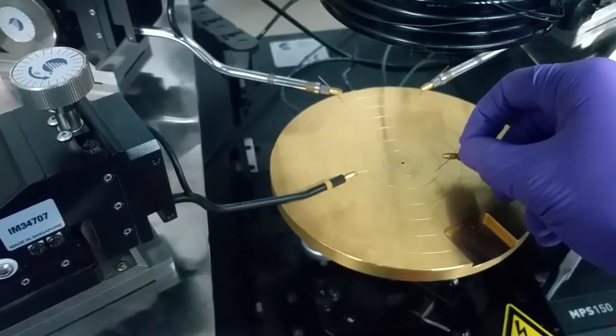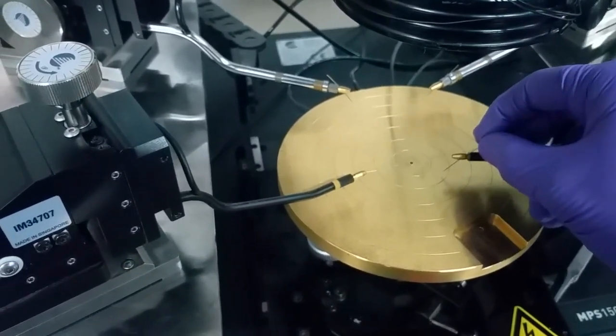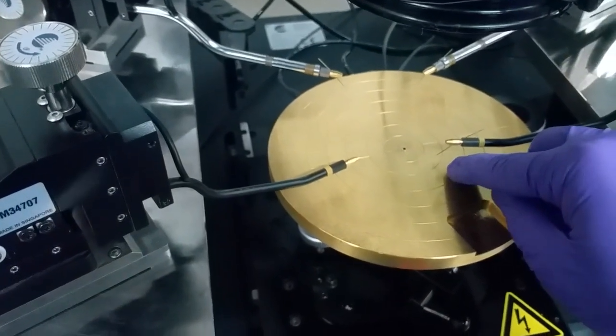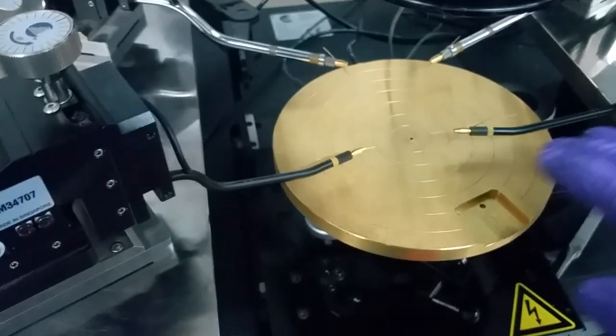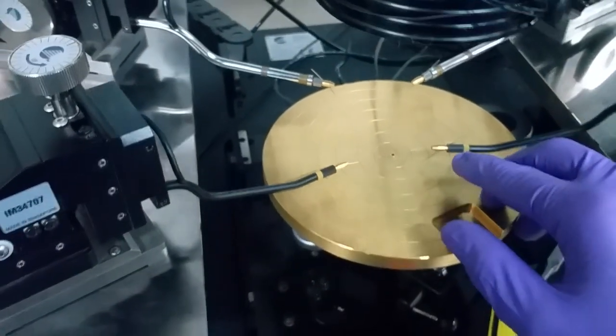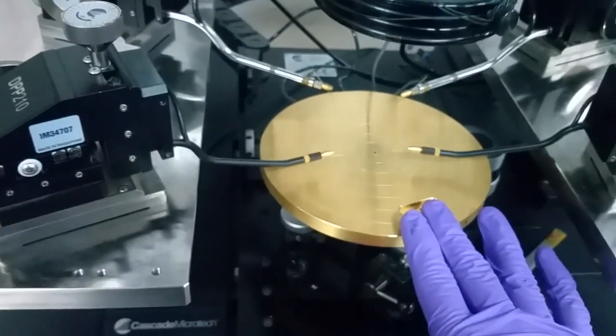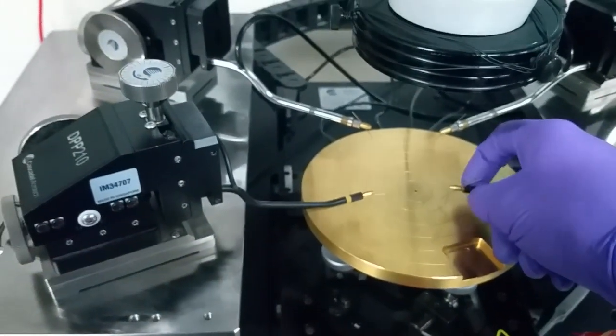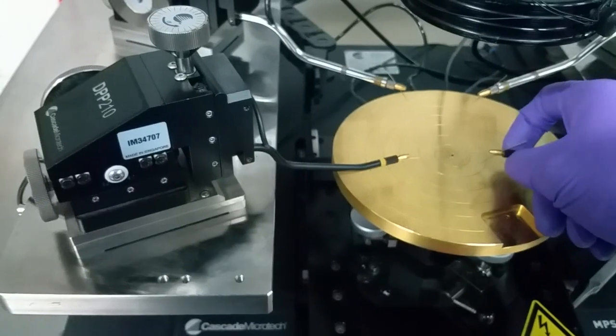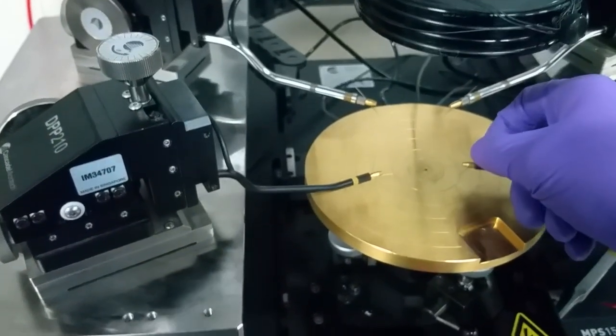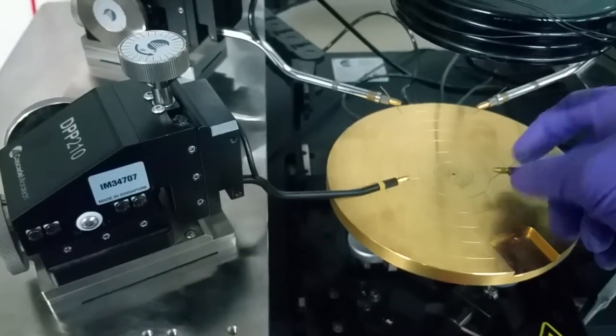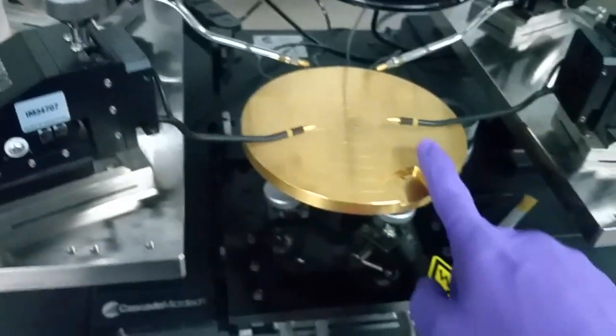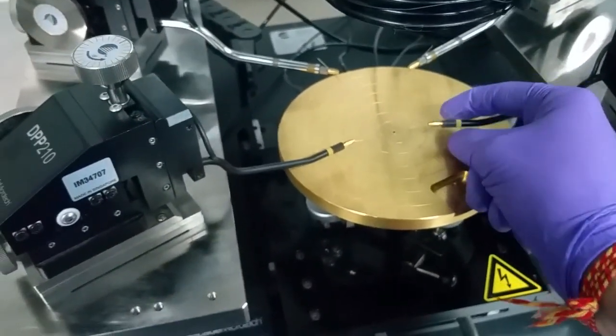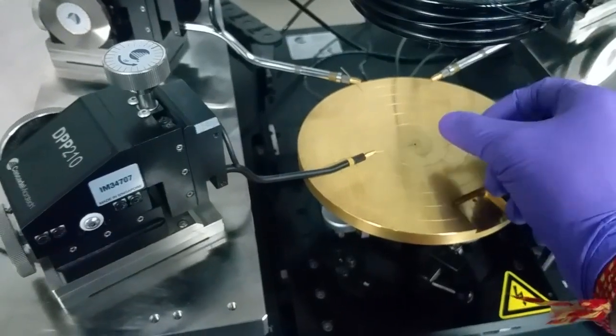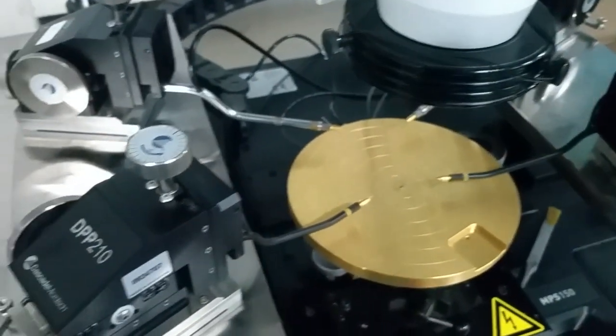Like earlier your probe was here, and when it touches, it will automatically move a little bit up. So it will not exert much pressure on the probe or your sample. Simply it will make the contact, and your probe life will be sustained. But in the other case, if you hold the probe tightly this way, then if you exert extra pressure or extra Z movement, it may damage the probe or the sample. So this is one tip I want you to use: you should loosen this probe here and then use it and connect to your sample.